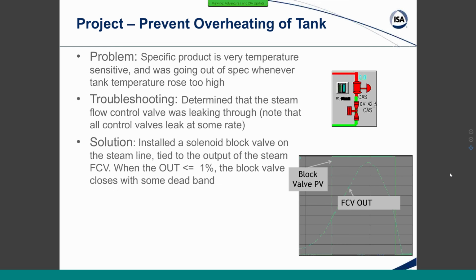So instead of trying to put in a control valve that had a really tight shutoff and wouldn't leak through as severely, we installed a block valve with a solenoid on the steam line prior to that control valve. And then we tied the block valve signal to the output of the control valve. So we've got our blue line in the little graph here. Whenever the output of that flow control valve got above 1%, you can see the block valve open. And then when it drops back down below that 1%, the block valve automatically closes.